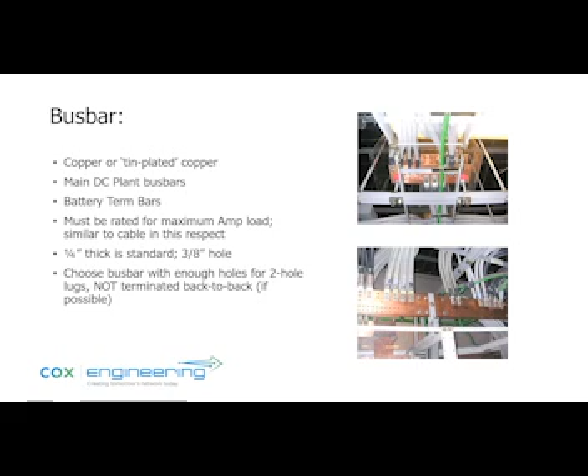Bus bar is what the cable is going to be connected to. And these are large copper bars that you'll see throughout the critical facility power room, the main DC plant bus bars, battery termination bars. They've got to be rated for the amp load, just like a cable would be.